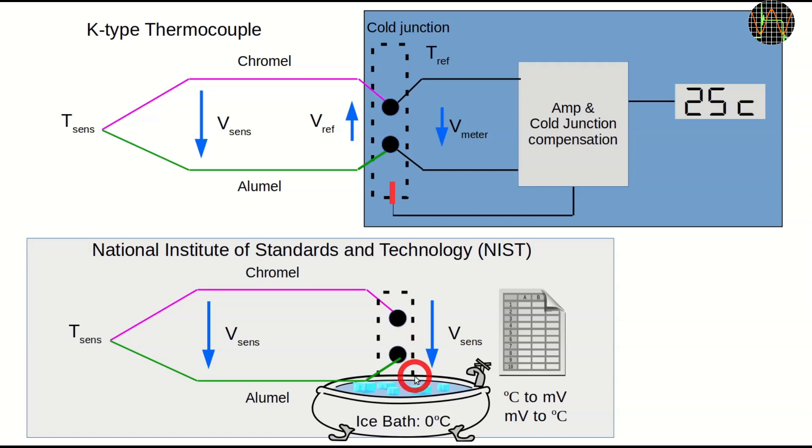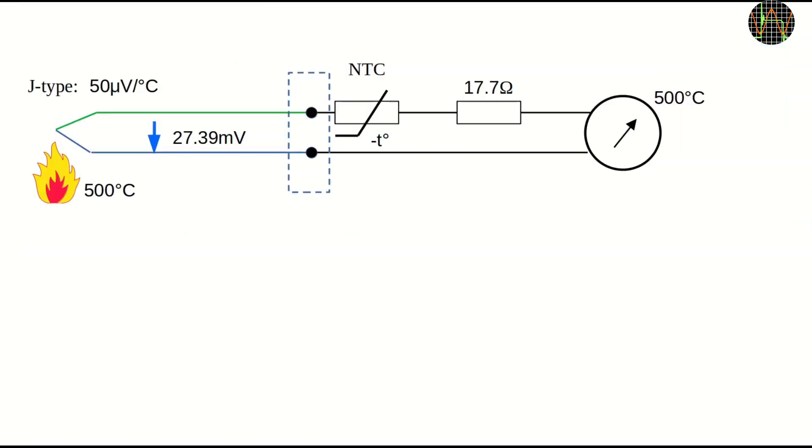Since keeping an ice bath in your meter is somewhat impractical, the workaround is to measure the actual temperature of the junction and simply correct the readings. In our case, the probe is say at 500 degrees Celsius and the instrument in the cold junction at 0 degrees Celsius.